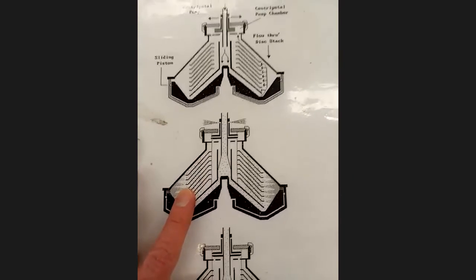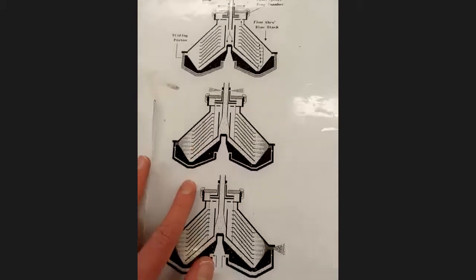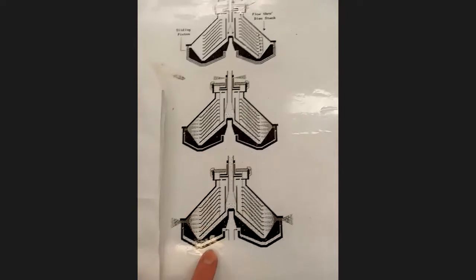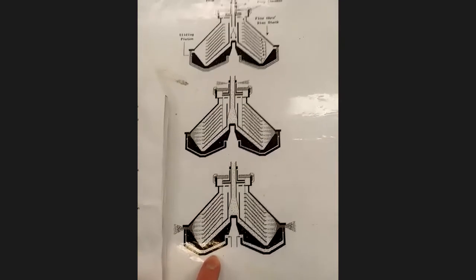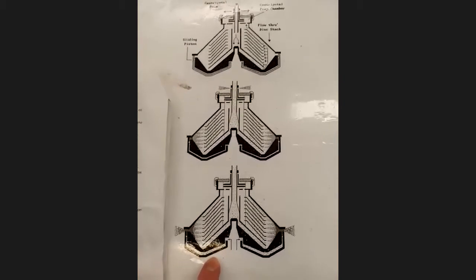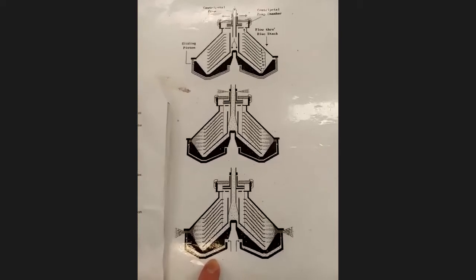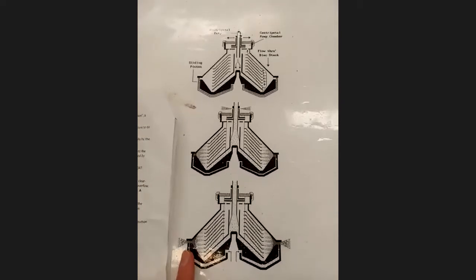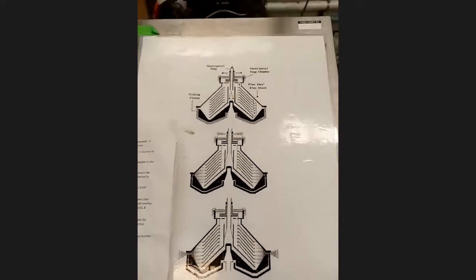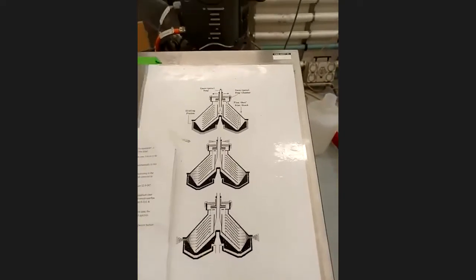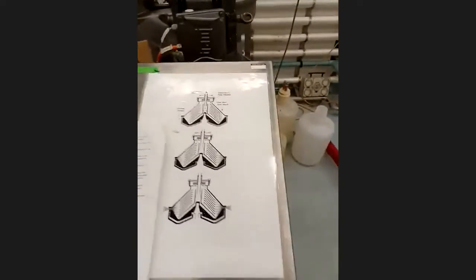Then that area is going to fill up with solids. Once it fills up with solids, we need to get rid of those solids. Water goes underneath the bowl and pushes the bowl up to expose a hole on the outside of the bowl. By exposing the hole, the high G inside the centrifuge sprays those solids out. Once those solids are out, the bowl closes once again, and we can separate solid away from liquid. So that is the solid-liquid separation process.